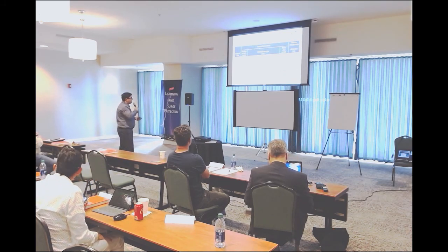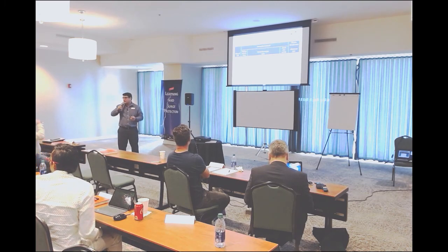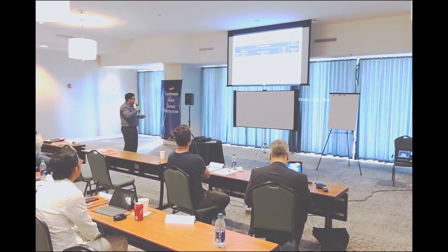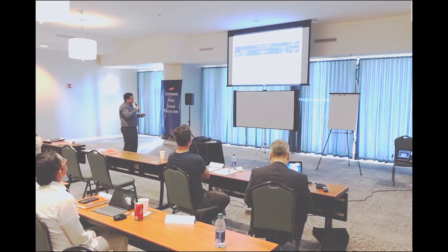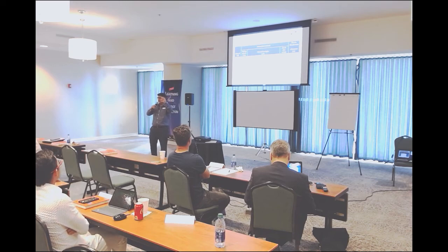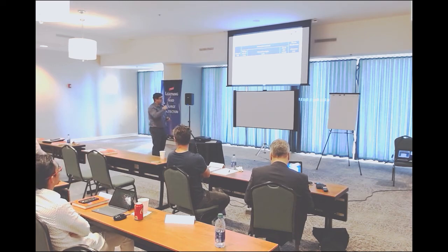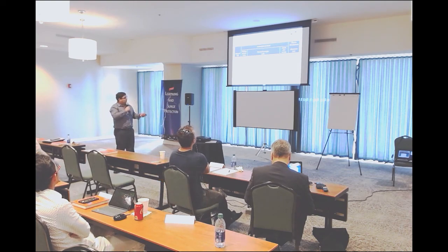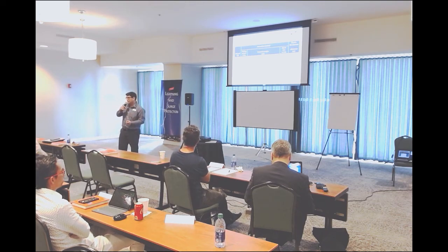So implementing the three different methods, you can see I've done the risk analysis. I know I've got an LPL4 system. That means I have to use a rolling sphere of 60 meters, and I have a protective angle. And if I'm using the protective angle method, you'll see that for an LPL4, your protective angle changes depending on the height of the air termination rod, or the height between the air termination rod and your reference, which is the floor or the roof of the building, whatever the case may be. And then there's your mesh sizes as well. And then obviously the next important concept is the down conductor system, which is basically providing you with typical distance values that you have to use for those downcomers. Great.